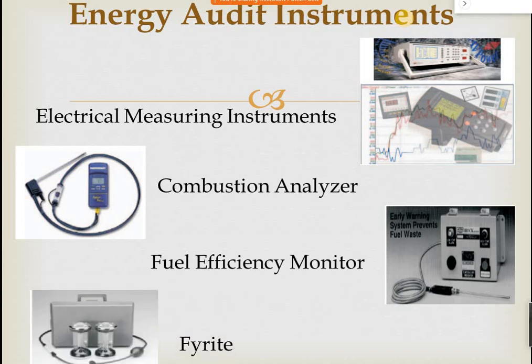So the requirement of energy audit such as identification and quantification of energy necessity measurement. These measurements require the use of instruments, and these instruments must be portable, durable, easy to operate and relatively inexpensive. The parameters generally monitored during energy audit include the following: basic electrical parameter in AC and DC system like voltage, current, power factor, active power, apparent power, demand, reactive power, frequency, harmonics, etc.